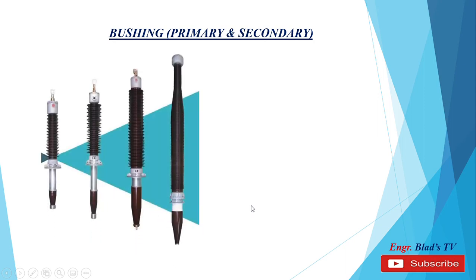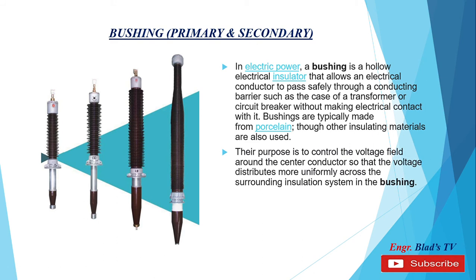Bushing — primary and secondary. In electrical power, a bushing is a hollow electrical insulator that allows an electrical conductor to pass safely through a conducting barrier, such as in a transformer or circuit breaker, without making electrical contact with it. Bushings are typically made from porcelain, though other insulating materials are also used. Their purpose is to control the voltage field around the center conductors so that the voltage distributes more uniformly across the surrounding insulation system in the bushing. In this picture we can see the different types of bushings, which are determined by the different types of system voltage.